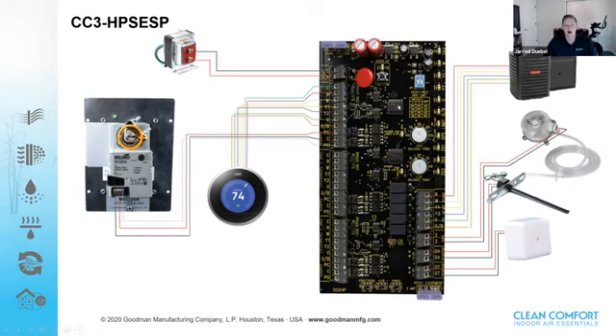Okay, so zone 1, zone 2 stat, zone 3 stat, again, correlating zone dampers are going to be right there. We have a couple other features on this panel. First of all, you got some dip switches up here at the top. That's to set the high limit. So on the 2 and 3 zone panels, we have a preset low limit. And when I say low limit, I'm referring to discharge air. It's just a safety that we build in. You don't have to use that feature, but you can. So the preset on the low limit is going to be 43 degrees.